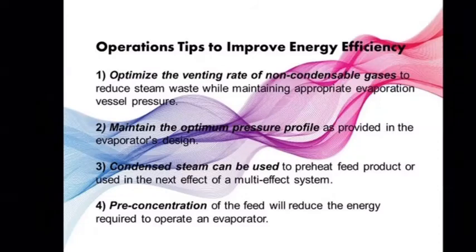Operation tips to improve energy efficiency. The following provides evaporating practices that can reduce energy consumption in your evaporators. First, optimize the venting rate of non-condensable gases to reduce steam waste while maintaining appropriate evaporation vessel pressure. Non-condensable gases in the evaporation vessel increase pressure, which increases the boiling point and heat requirements. Second, maintain the optimum pressure profile as provided in the evaporator's design. Excess pressure inhibits evaporation by raising the boiling point. Third, condensed steam can be used to preheat feed product or used in the next effect of a multi-effect system.